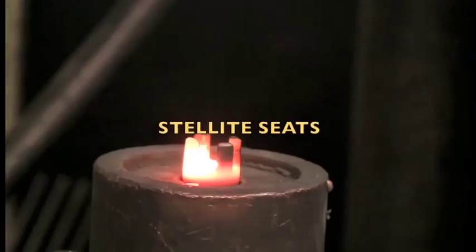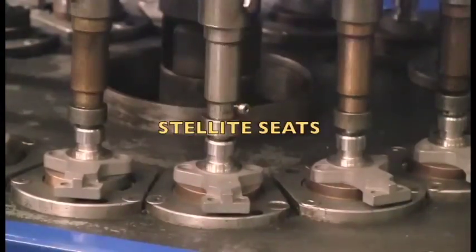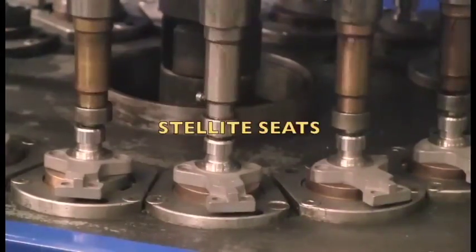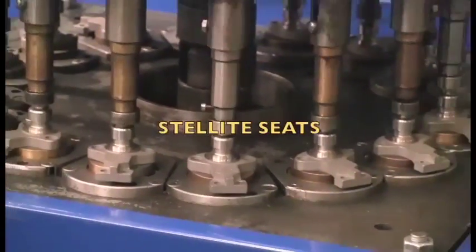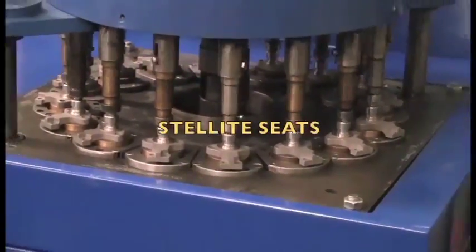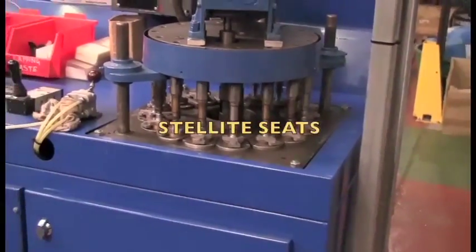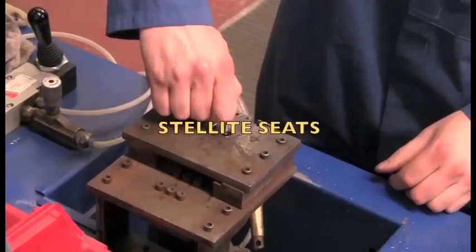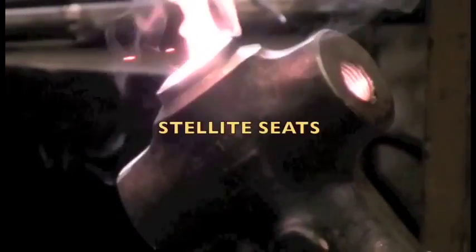Stellite 6 is welded into the seat facings of all steam traps manufactured by Velan. The resistance of Stellite 6 to erosion and wire drawing is over 3 times that of induction-hardened stainless steel. The result is a steam trap that routinely lasts up to 3 times longer than conventional designs under the same service conditions. Velan is currently the only manufacturer globally to use stellite as a standard material in the construction of a steam trap, and the value is well proven.